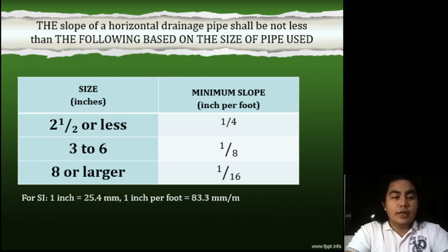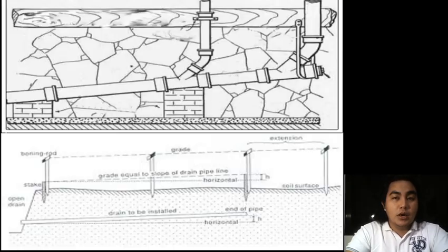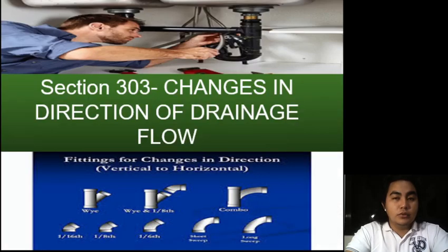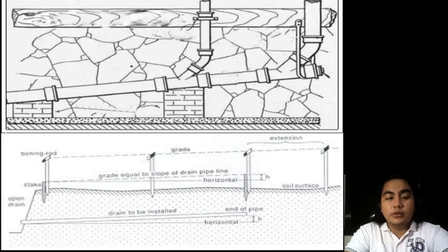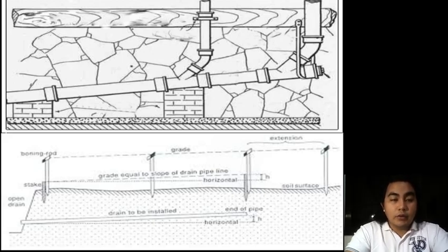The ideal slope of any drain line is 1/4 inch per foot of pipe. In other words, for every foot the pipe travels horizontally, it should be dropping 1/4 inch vertically. Many drains have either too little slope or too much slope. Overslope pipes, greater than 1/2 inch per foot, are as likely to clog as undersloped ones because the liquids move too fast and leave the solids behind. This must be taken into consideration to avoid backflow, clogging, and future problems.